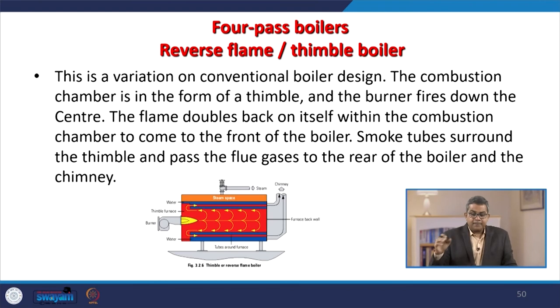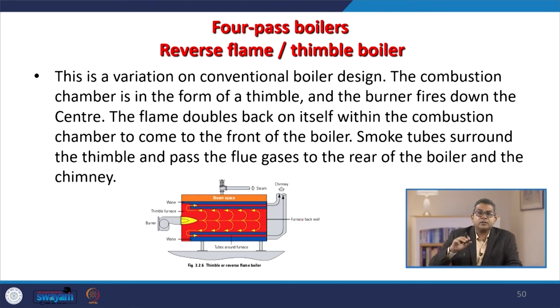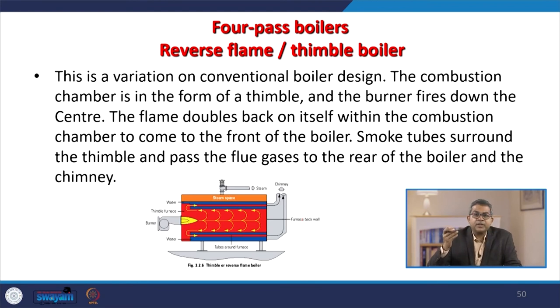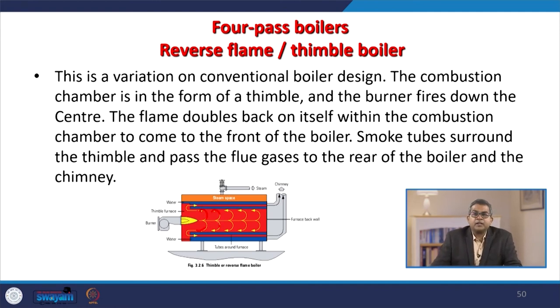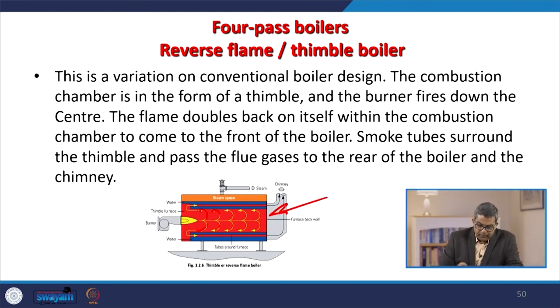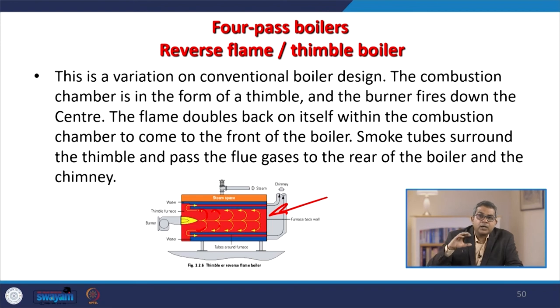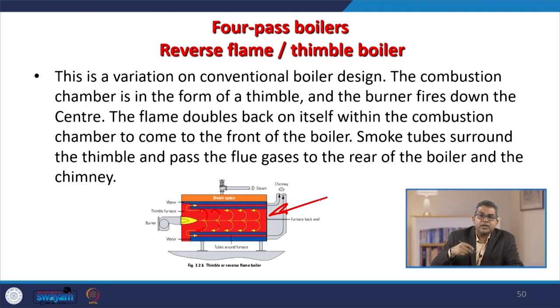Another category is the 4-pass boiler, also called a reverse flame or thimble type boiler. This is a variation on conventional boiler design where the combustion chamber is in the form of a thimble, and the burner fires down the centre. The flame doubles back on itself within the combustion chamber to come to the front of the boiler. Smoke tubes surround the thimble and pass flue gases to the rear of the boiler and chimney.